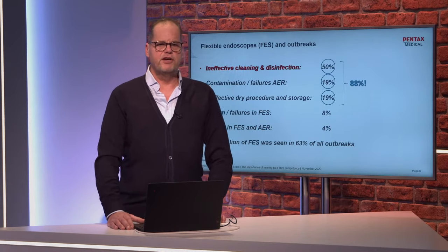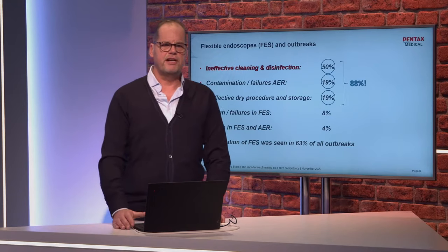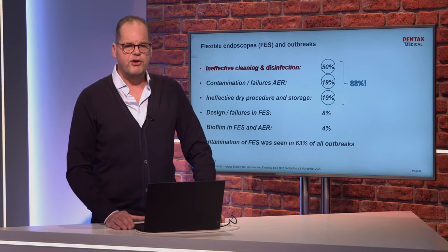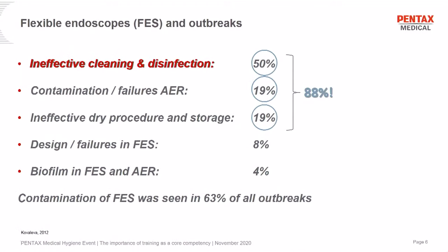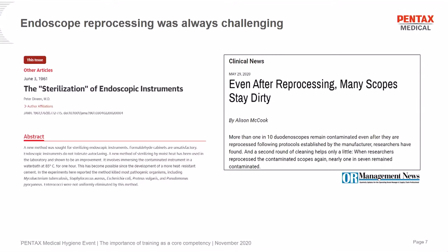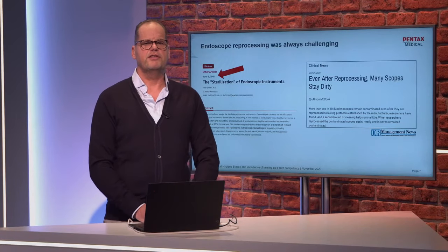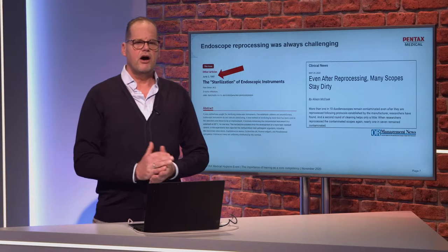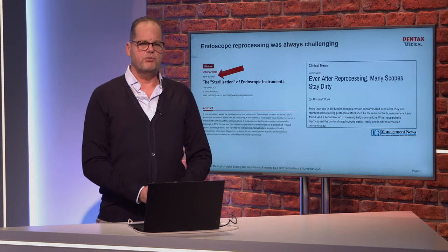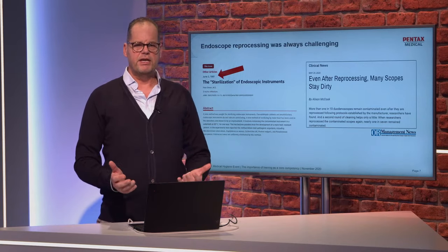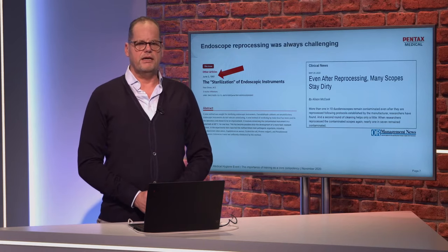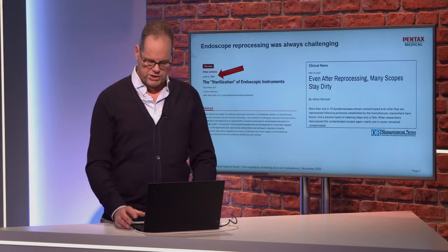So looking at the first three—ineffective cleaning, contamination, and ineffective dry procedures—they contribute to almost 90% of outbreaks. It was always challenging. Endoscope reprocessing was already a problem in the 1960s, which was published at the time. And even today, many scopes stay dirty even after reprocessing.